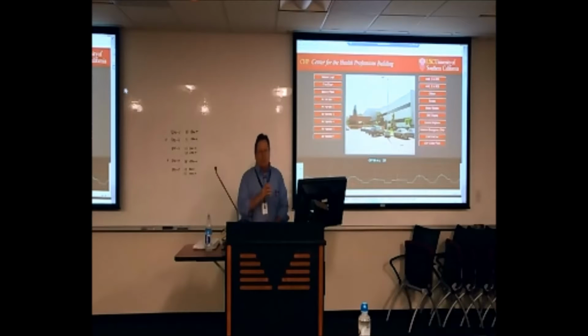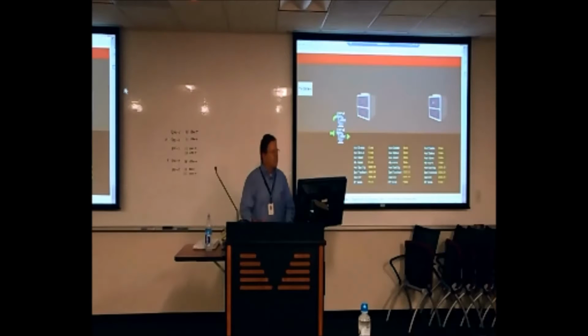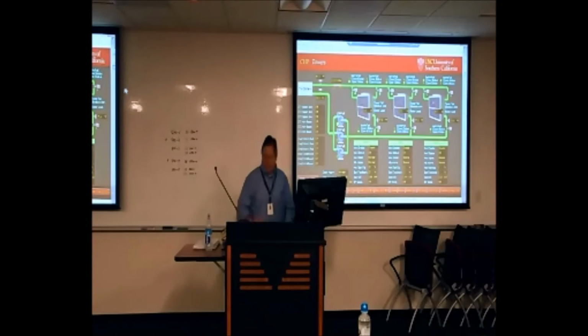So the central plant at this point now is getting a brand new chiller number 1. I'll explain a little bit more shortly how that might affect the sequence, but right now we built in some of the hooks we need to allow that new central plant with its new chiller to coexist with this cooling tower project we just put in. So first off, we're in the CHP graphics display right here. I'll click on towers, and this brings us into our cooling tower graphic.